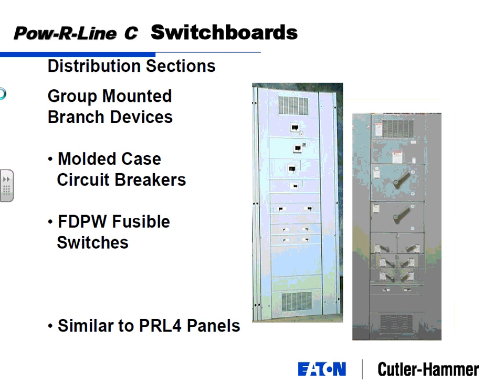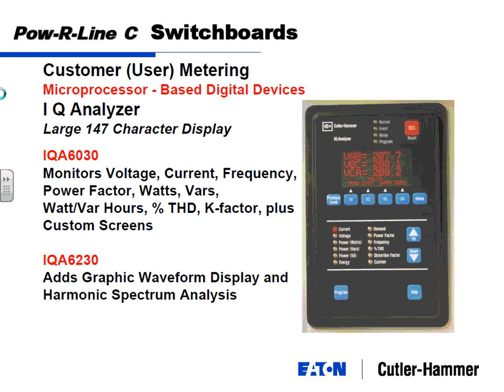All these meters today, not these meters, but our new meter family, have the capability to have embedded web servers or Ethernet communication like Modbus TCP/IP, or what have you. And if you're designing a building from scratch, you put your customer meter in there. All you basically need to do is put a LAN or some kind of Ethernet jack in the electrical equipment room, and you can tap right into the meter.